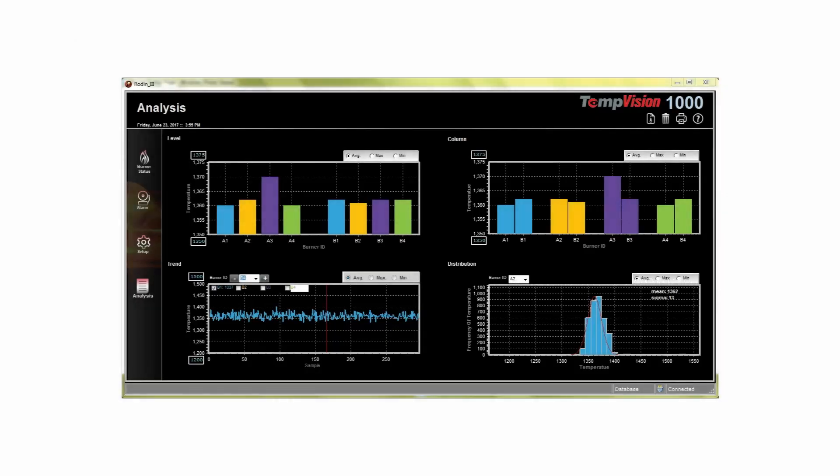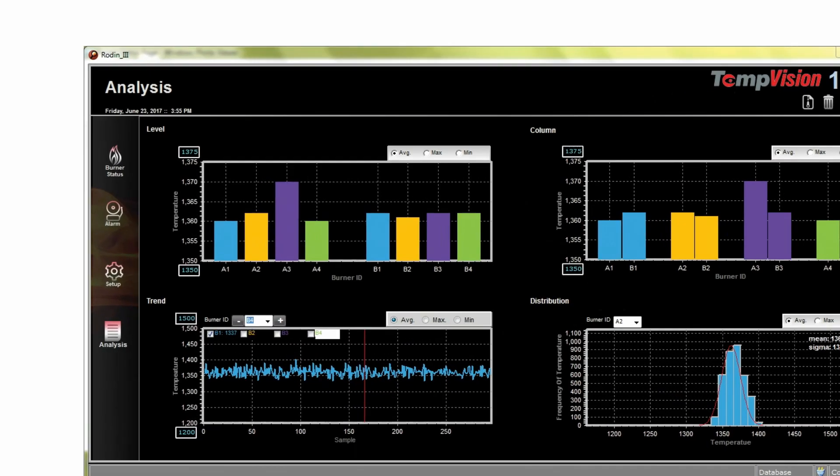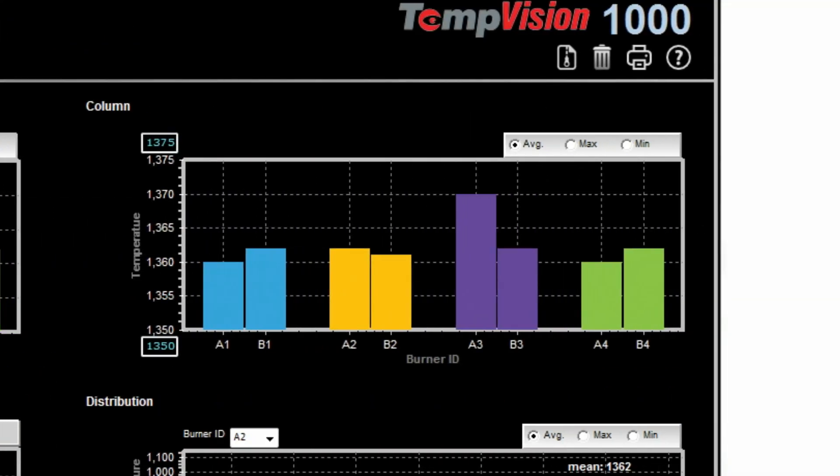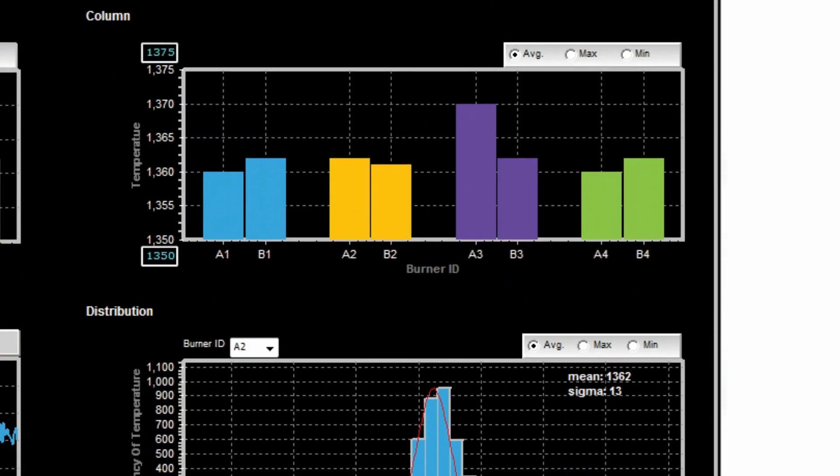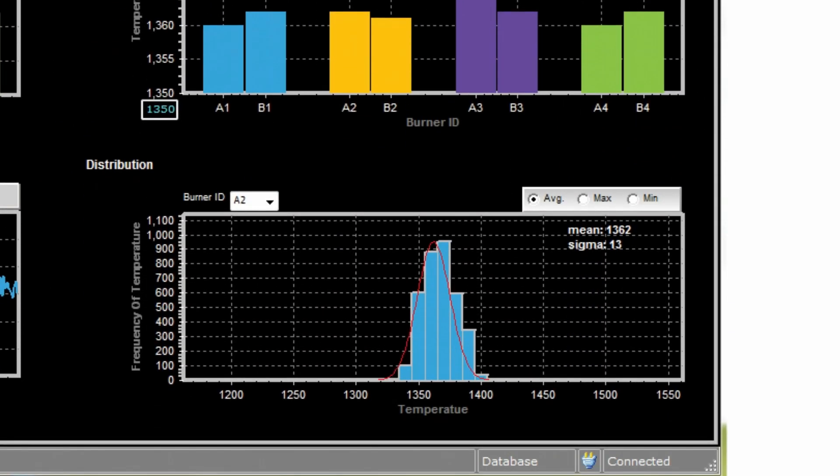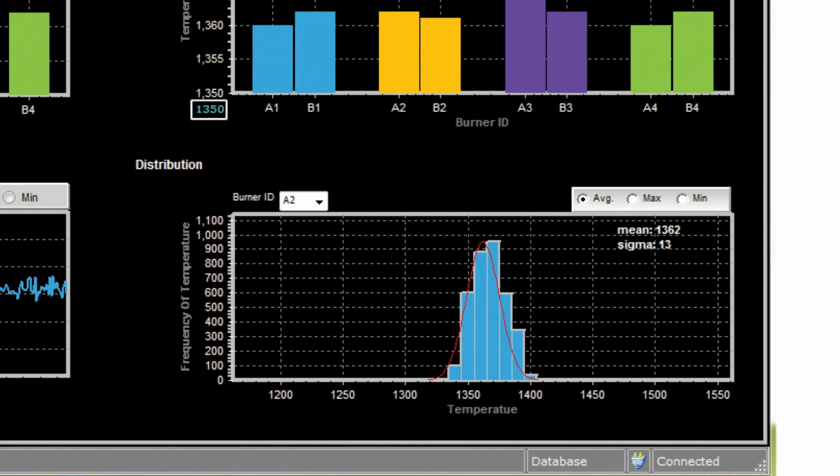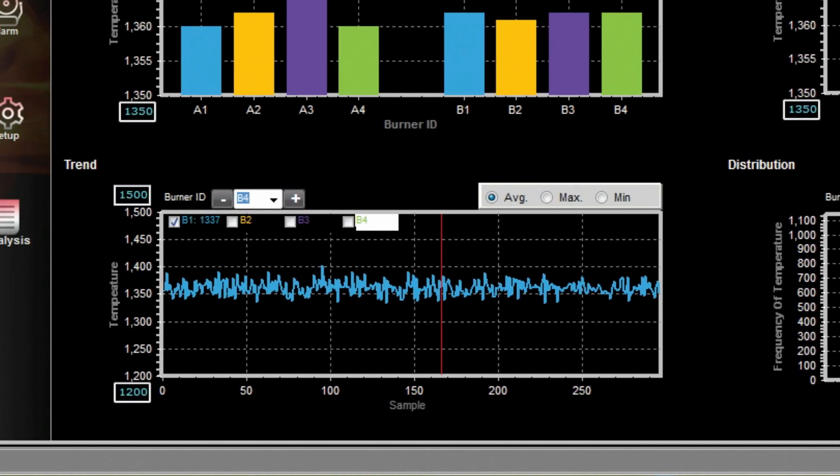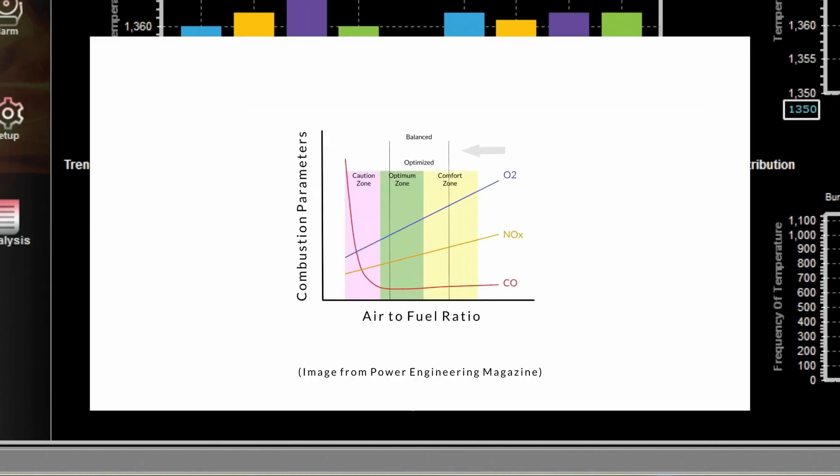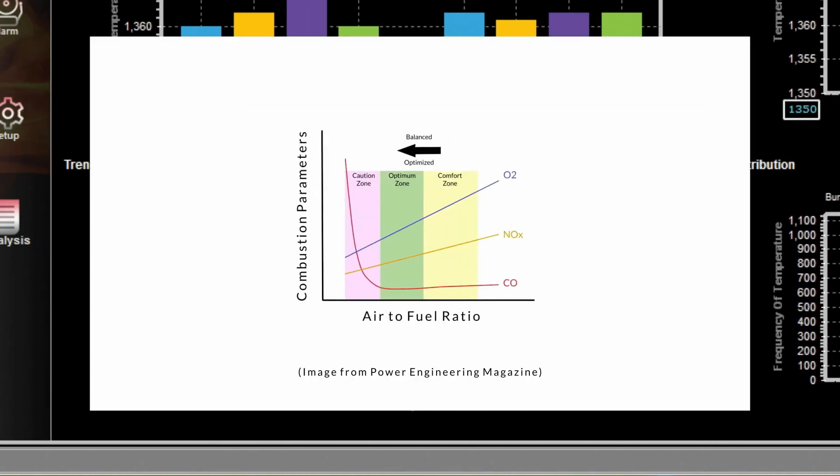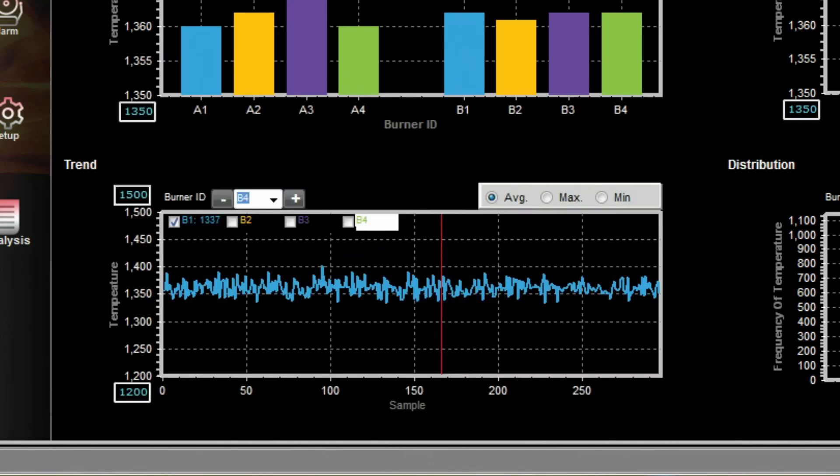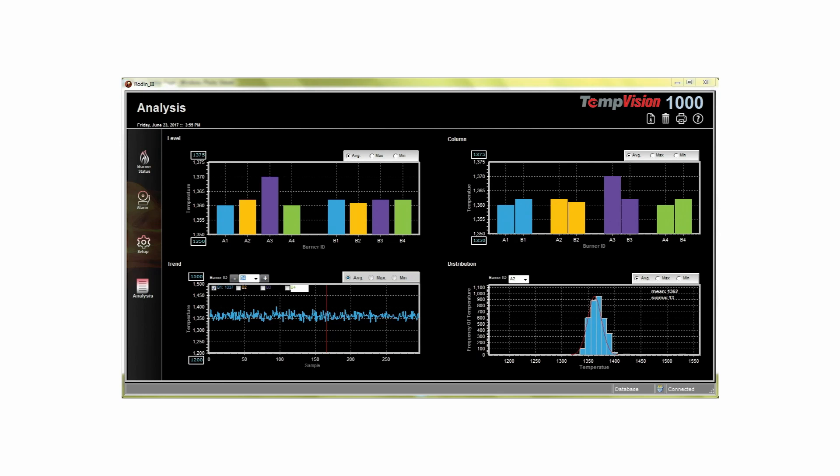Actionable data is obtained once temperature profiles of multiple burners are collected. The software can then easily process, analyze, and present data intuitively, allowing the operator to make adjustments to boiler variables such as air and fuel ratios. Changes in the burner's performance will be reflected in the temperature profile which operators can use to guide them towards improvements.